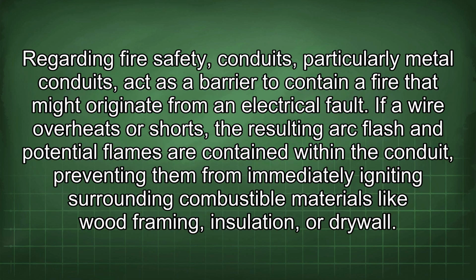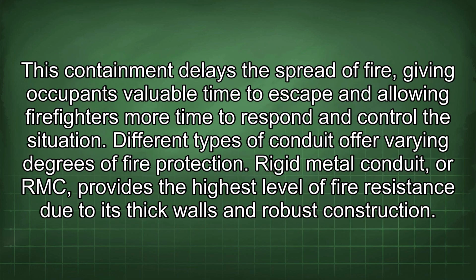Regarding fire safety, conduits, particularly metal conduits, act as a barrier to contain a fire that might originate from an electrical fault. If a wire overheats or shorts, the resulting arc flash and potential flames are contained within the conduit, preventing them from immediately igniting surrounding combustible materials like wood framing, insulation, or drywall. This containment delays the spread of fire, giving occupants valuable time to escape and allowing firefighters more time to respond and control the situation. Different types of conduit offer varying degrees of fire protection.